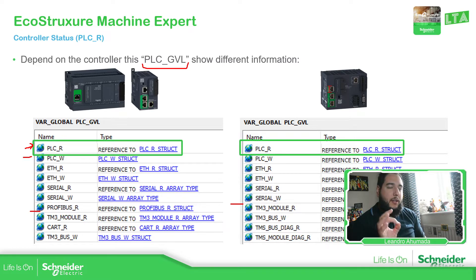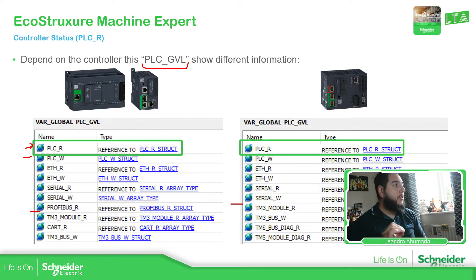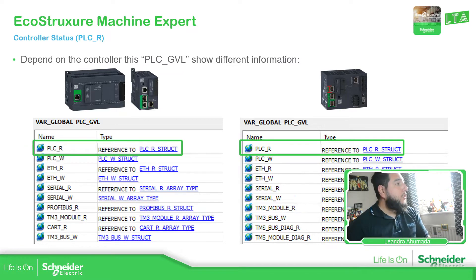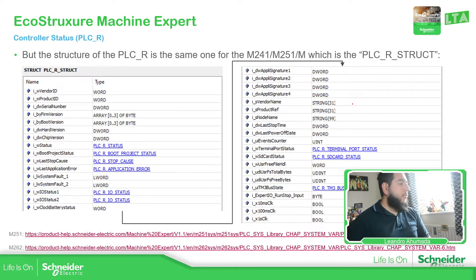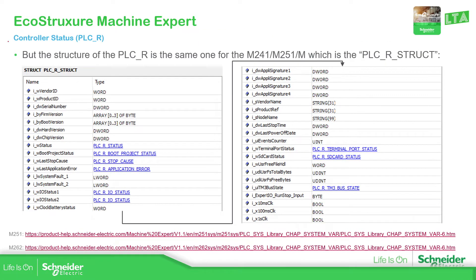The one that allows us to see what's really going on inside the PLC is the one that is PLC underscore R, for Romeo. If we dig more inside this PLC underscore R, we can see that we have this information. This is the information that we have in this extract chart — this type of structure. You can see that you have the vendor, and then you have: status, boot project status, last stop cause, system fault, IO status, and also the clock and battery check.